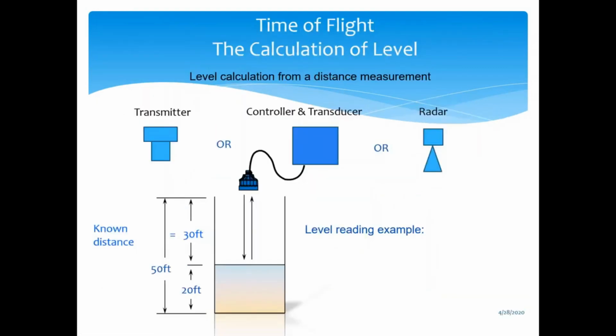So again, I kind of already explained this, but once you know the distance from the transducer down to your liquid level, we simply take the span that the transmitter is programmed for, we subtract out that distance, and that tells you the level inside of your tank or your vessel. That works the same with radar or ultrasonic.